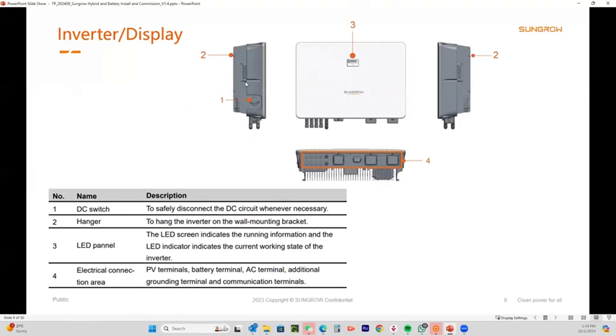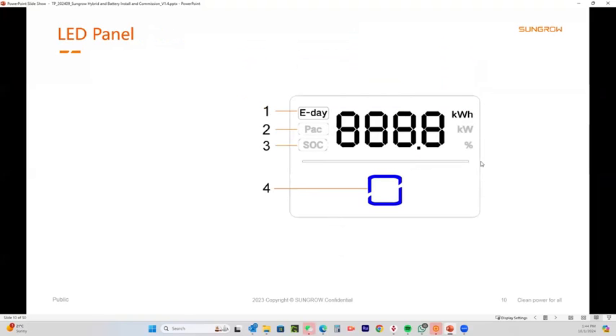On the left hand side, we have the DC isolator. That's built in and it's all fully compliant. On the front, we have an LED panel, nothing much on the right hand side there. All the plug and play connections are along the bottom end, and it is true plug and play. The LED panel in the front is a high brightness panel, and it will show daily energy, that is the total energy for today, current AC power in kilowatts, and the current state of charge of the battery. There's a blue LED here as well, which if it's on steady, it means the inverter's all working fine.